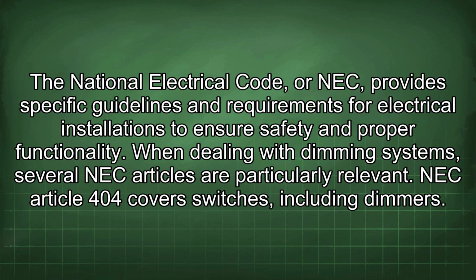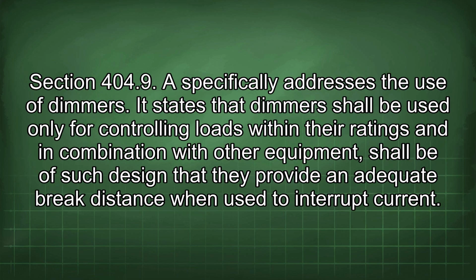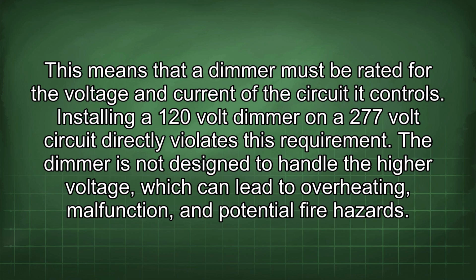The National Electrical Code, or NEC, provides specific guidelines and requirements for electrical installations to ensure safety and proper functionality. When dealing with dimming systems, several NEC articles are particularly relevant. NEC Article 404 covers switches, including dimmers. Section 404.9 specifically addresses the use of dimmers. It states that dimmers shall be used only for controlling loads within the ratings and, in combination with other equipment, shall be of such design that they provide an adequate break distance when used to interrupt current. This means that a dimmer must be rated for the voltage and current of the circuit it controls.